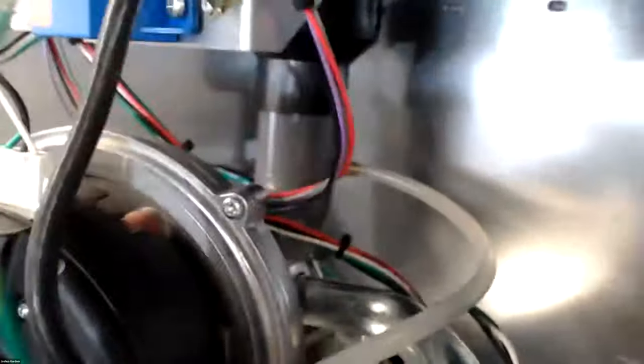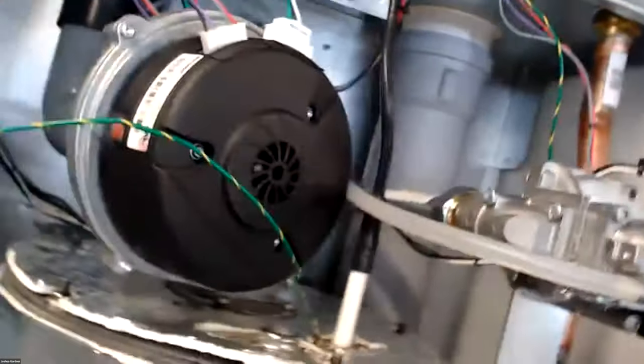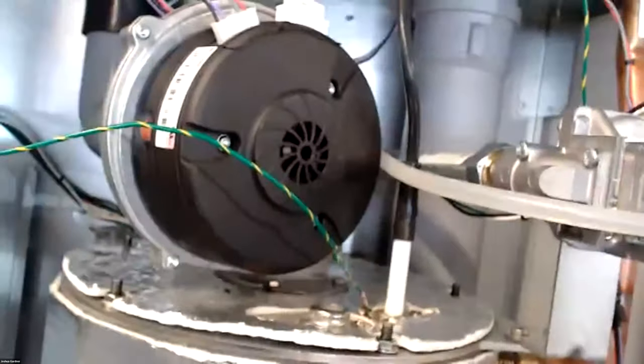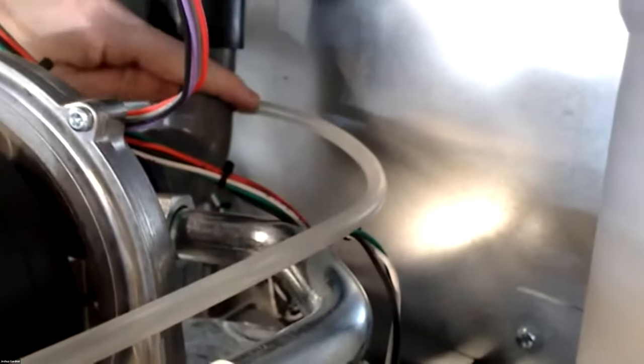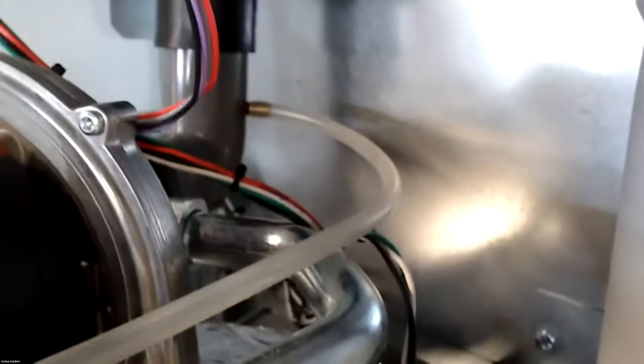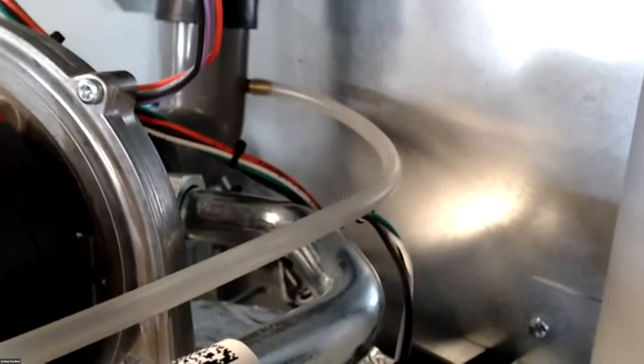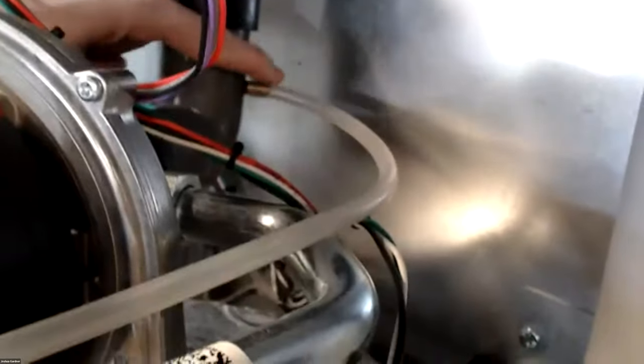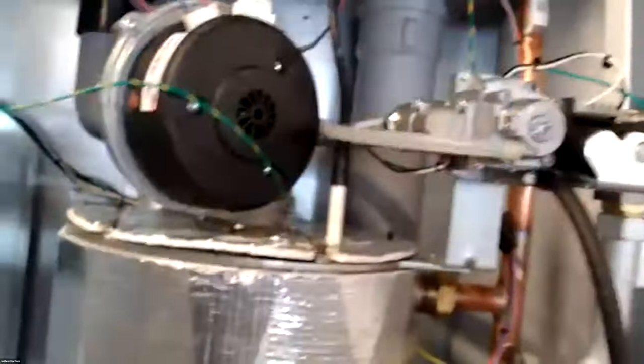So the venturi then goes into the fan. We have our gas tube coming over in here, and then we have our air regulation right here, all right? That comes through and ties into our gas valves for the firing rate. So one thing also to note during service, look at this gas tube, look at this brass connector in here, make sure you don't get debris. If you're using PVC, make sure you get all the shavings out of your pipe before you install this. That way we don't get PVC shavings up in here and clog this up and prevent our gas valve from opening up or going into high fire.